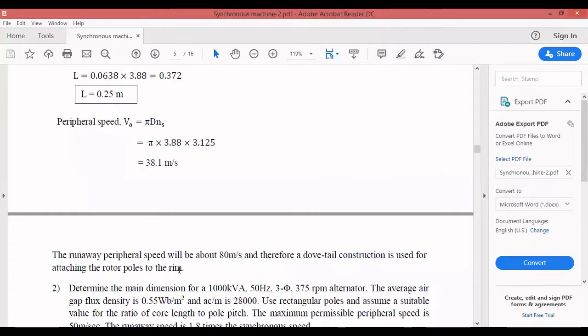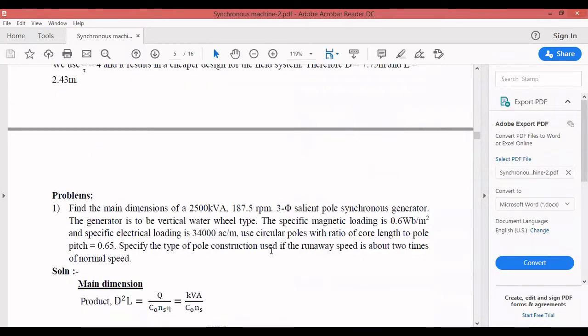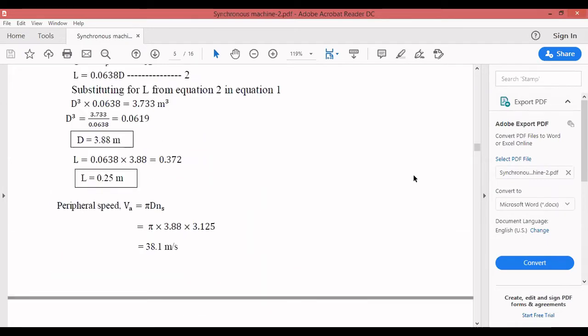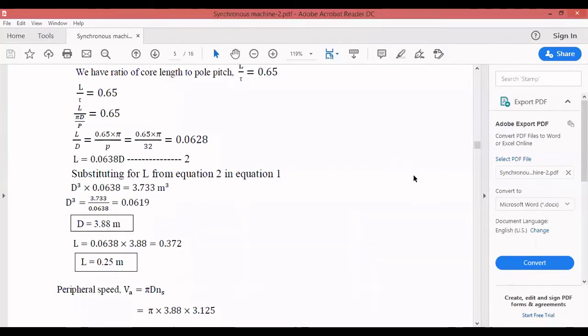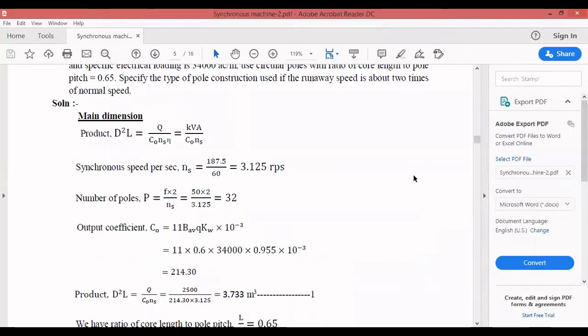Since the runaway peripheral speed is approximately 76.4 m/s (≈ 80 m/s), which exceeds the limit for circular pole construction, dovetail construction must be used for attaching the rotor poles to the rotor drum. Dovetail construction allows speeds up to 80 m/s. Therefore, for this problem we cannot use circular poles; instead, dovetail construction is used.